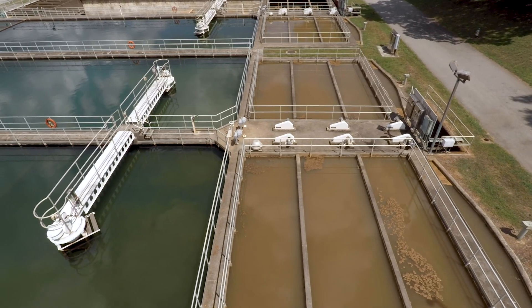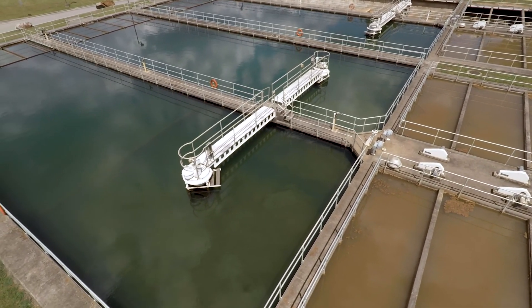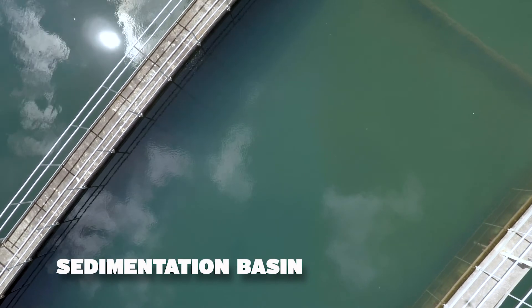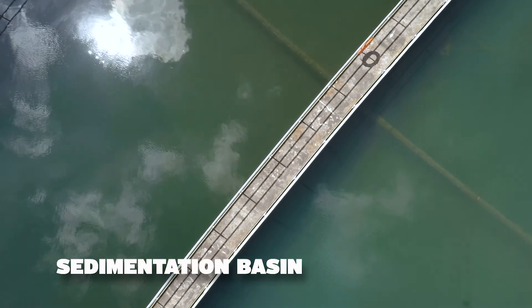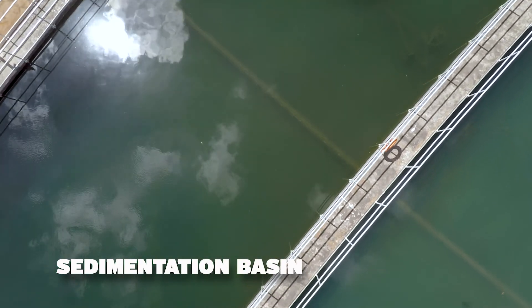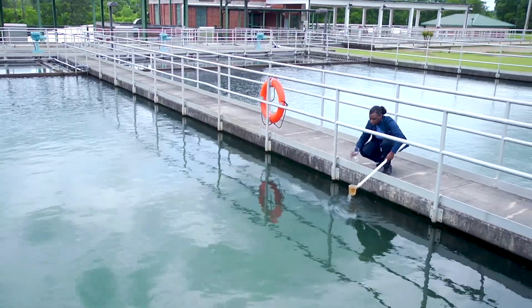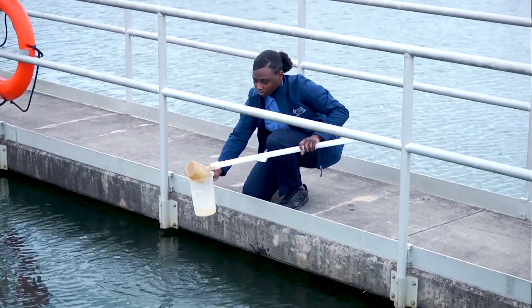Floc isn't the prettiest stuff in the world, but it's mainly just dirt particles. From the flocculation chamber, the water then flows into the sedimentation basin, and this is where things really start to settle down. In the sedimentation basin, the water is kept very still for about four hours. The floc is heavy, which means it will sink to the bottom of the basin, where it's slowly pushed out with a sludge sweep. At this point, we've removed any large particles from the water — the water is looking good and clear, but we still have a few more treatments to do.